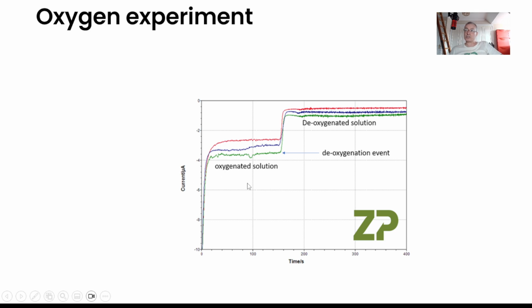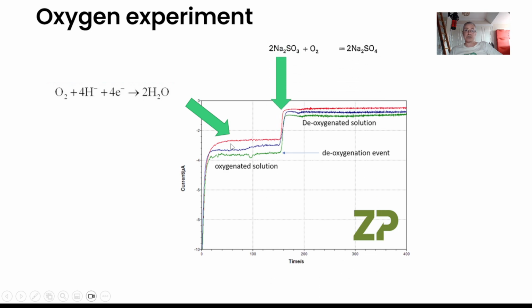This is what one of our oxygen sensors looks like. This is an oxygenated solution, about 6 parts per million of oxygen. And we get a current due to the electrochemical reduction of oxygen at about minus 600 to minus 650 millivolts. And then if we scavenge that oxygen, the signal goes close to zero. That's a little bit like your signal looks like.